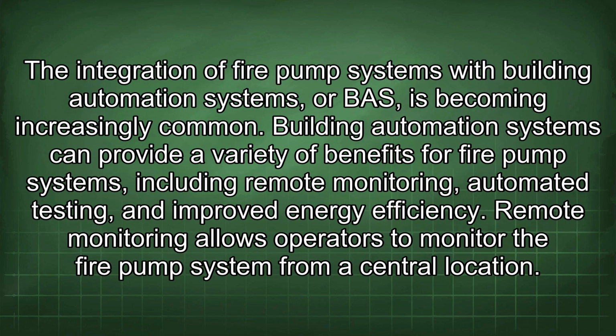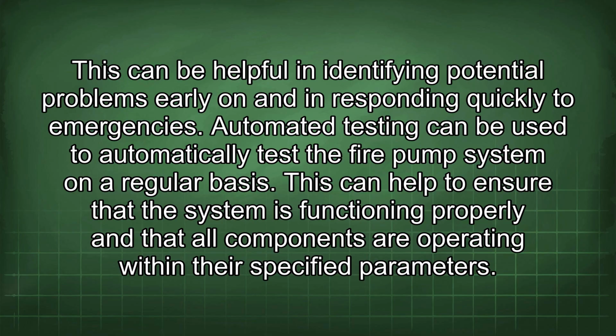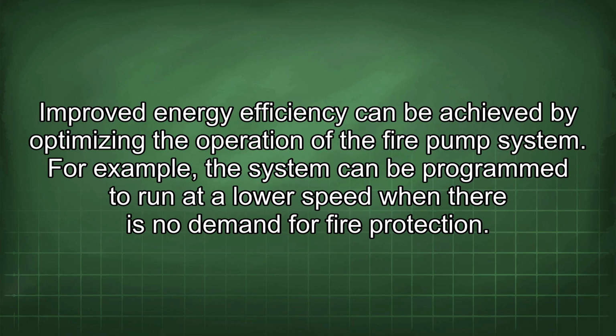The integration of fire pump systems with building automation systems, or BAS, is becoming increasingly common. Building automation systems can provide a variety of benefits for fire pump systems, including remote monitoring, automated testing, and improved energy efficiency. Remote monitoring allows operators to monitor the fire pump system from a central location. This can be helpful in identifying potential problems early on and in responding quickly to emergencies. Automated testing can be used to automatically test the fire pump system on a regular basis. This can help to ensure that the system is functioning properly and that all components are operating within their specified parameters. Improved energy efficiency can be achieved by optimizing the operation of the fire pump system. For example, the system can be programmed to run at a lower speed when there is no demand for fire protection.